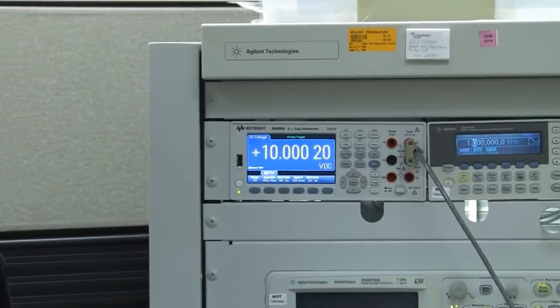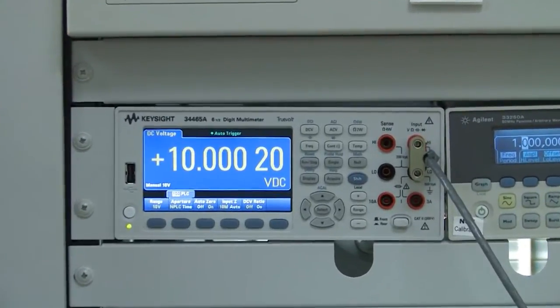By performing another auto calibration, we can remove the error caused by the increase in ambient and internal instrument temperatures.